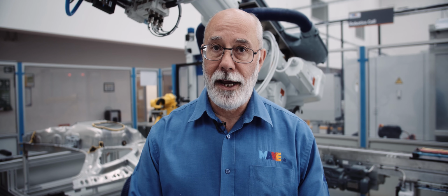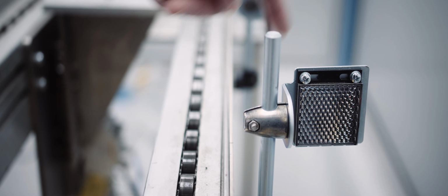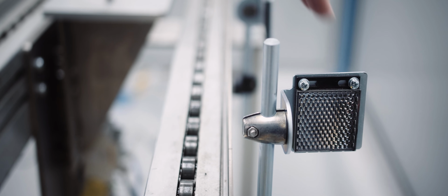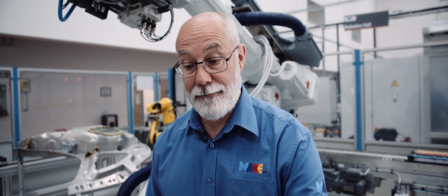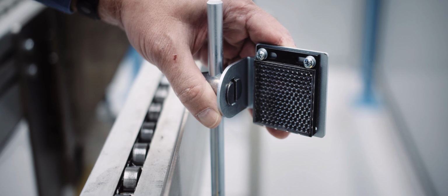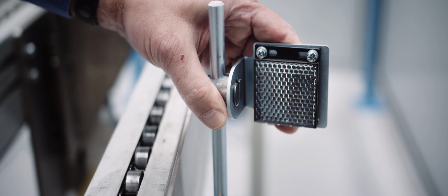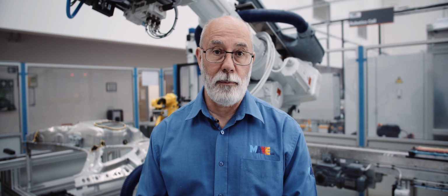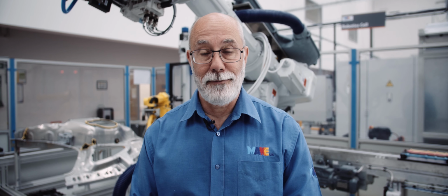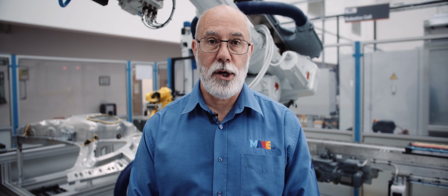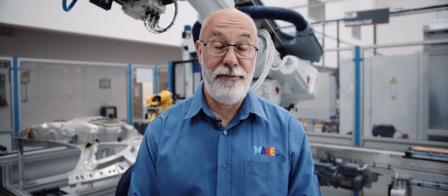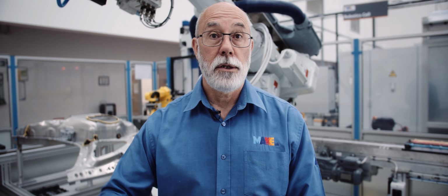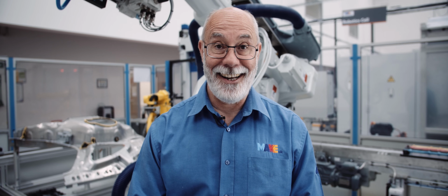Now, because of the location of the plate, I know that it's not part of something that's moved on the production line which has moved it. When I actually put my hand on the plate to move it, I can find that it moves fairly easily. So the problem there is not just the fact somebody's gone past it, it's moving easily. Ask the question why. Why is it moving easily? Because it hasn't been fitted or tightened correctly. So the solution now is to tighten it correctly.